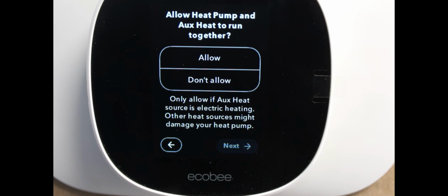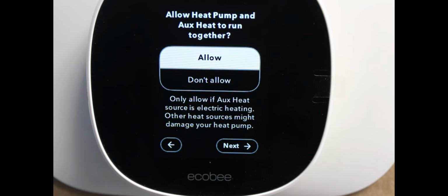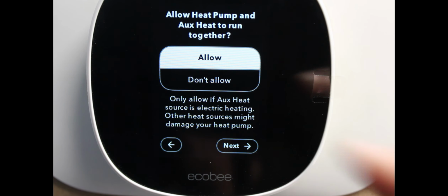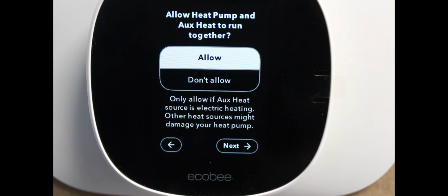Allow heat pump and auxiliary heat to run together. So this is a feature that's asking when it's time to heat, do we want to be able to use the auxiliary heat source with the heat pump? And we're going to allow that. The only times you wouldn't allow it is if it's a hybrid unit, meaning the backup heat source is a gas or propane appliance. And it actually even has a note that says only allow if the backup heat source is electric.